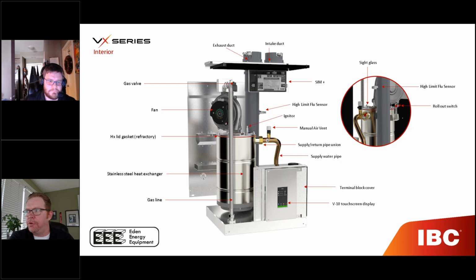Chris, do you want to just walk everybody through the rollout switch? Yeah, just like a traditional boiler, it's ensuring that if that gasket does ever fail, or if you have an issue in the cabinet, it's an additional safety. There are a lot of safety sensors in this boiler, and a lot of times it'll lock out before it ever gets to that rollout sensor, but it's nice to have. It's kind of a backup, a traditional code requirement, but it's nice to have in the back of the cabinet there to protect your owners and your site from any potential damage.